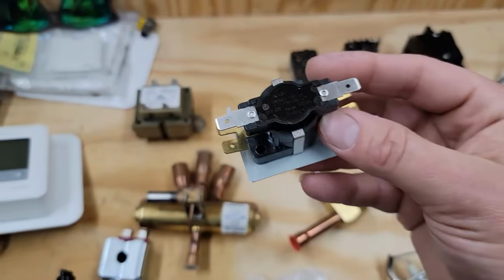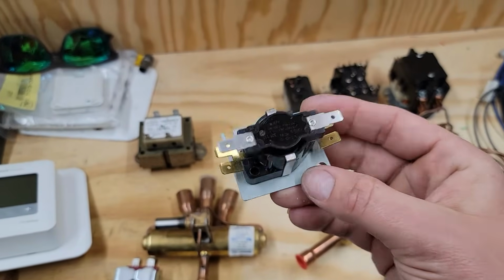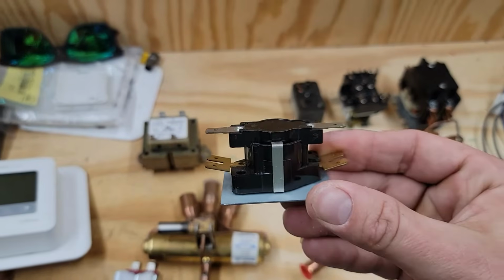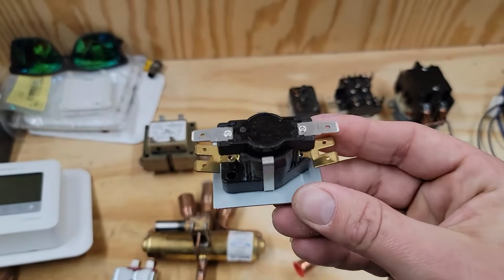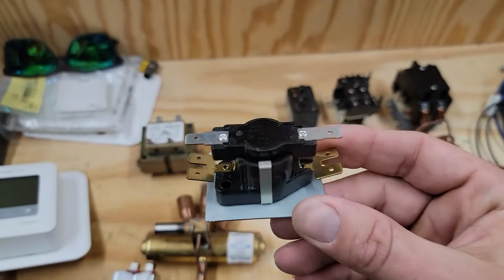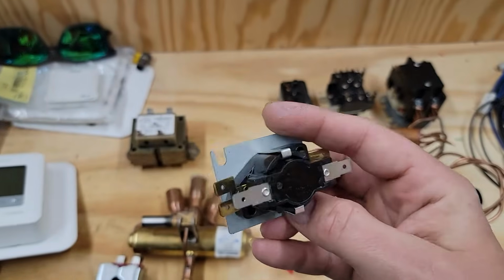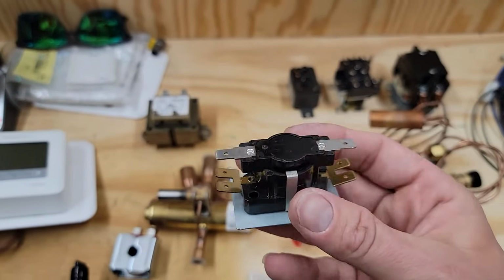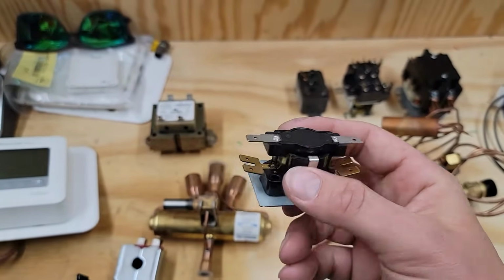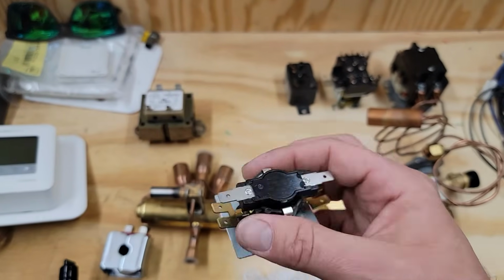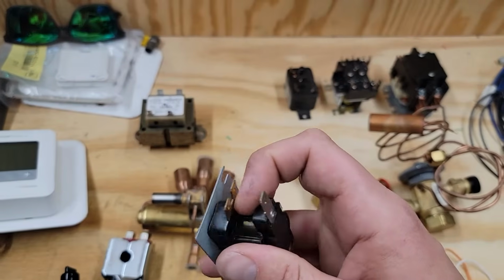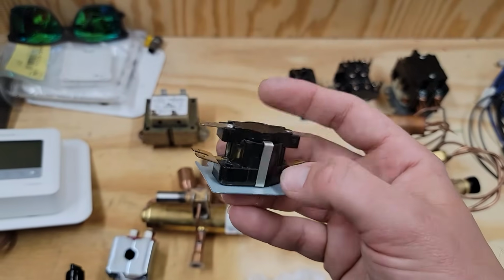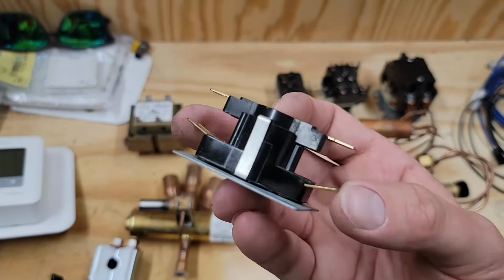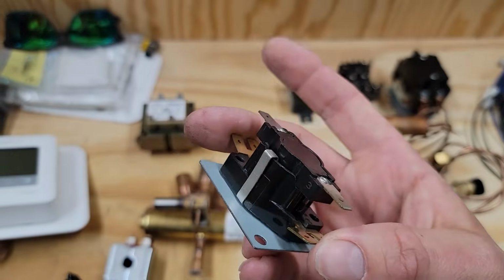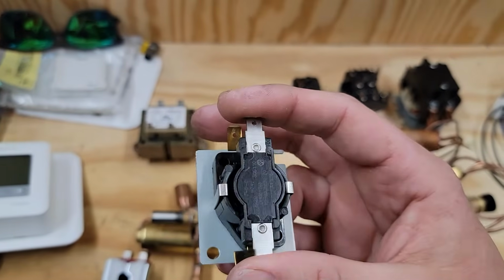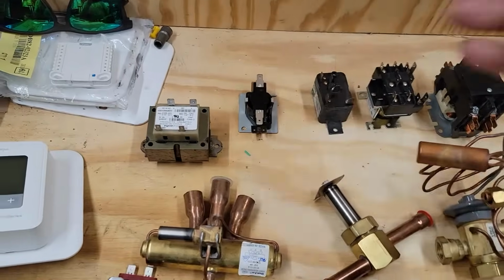All right, so our first relay here is a sequencer. A sequencer is typically used to control heat strips in a straight electric furnace or a heat pump's backup heat, and these typically go bad, especially in trailers. Sometimes you'll see them burnt, and sometimes when you take them out, this piece right here will just come right up off of this bottom part where the coil is. This is the coil, this is where your low voltage goes, and this is where your high voltage goes right here, okay? That's a sequencer.